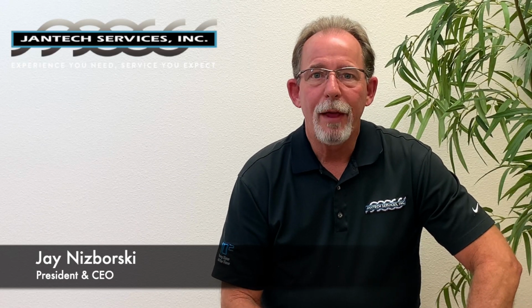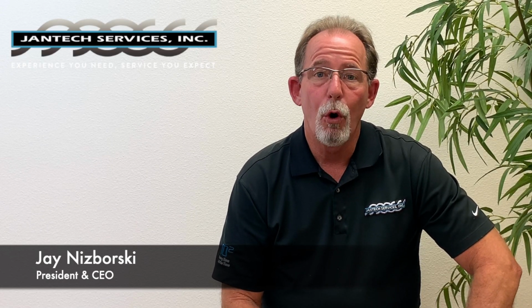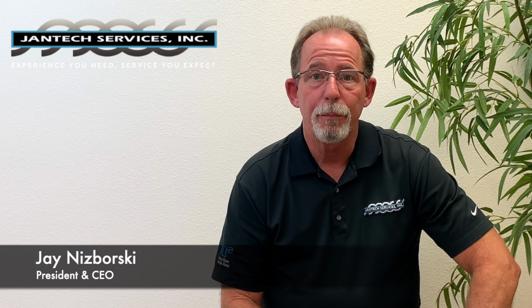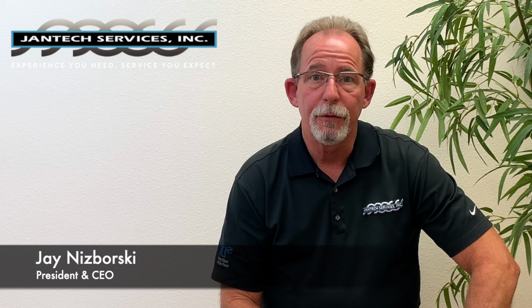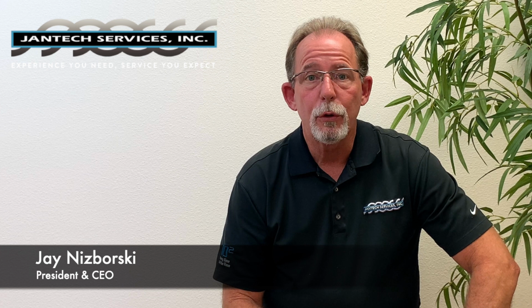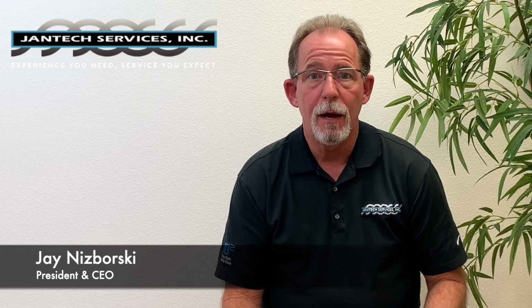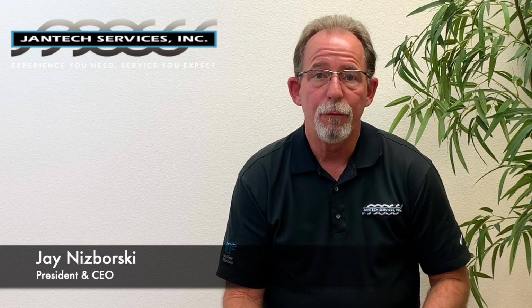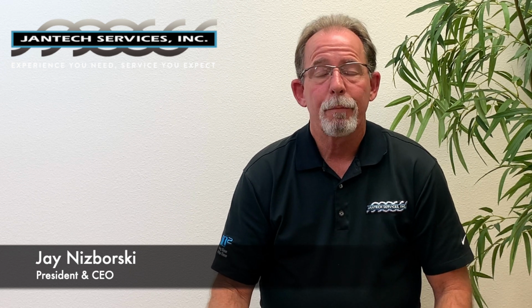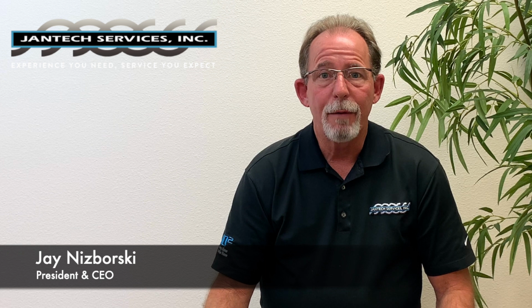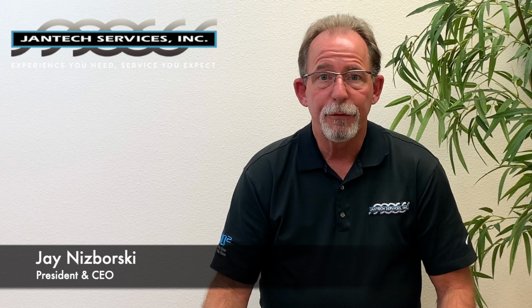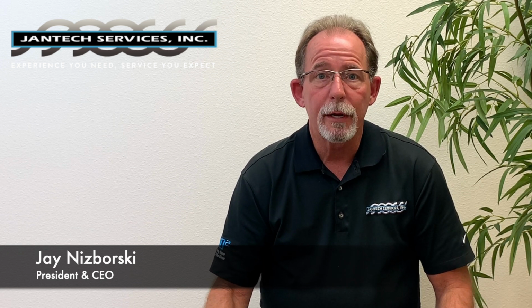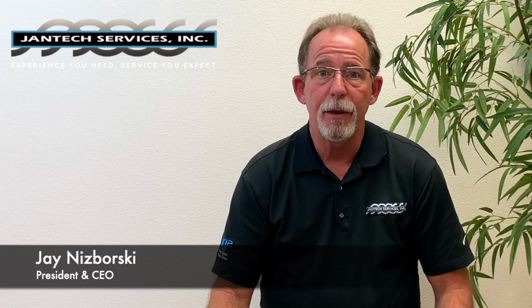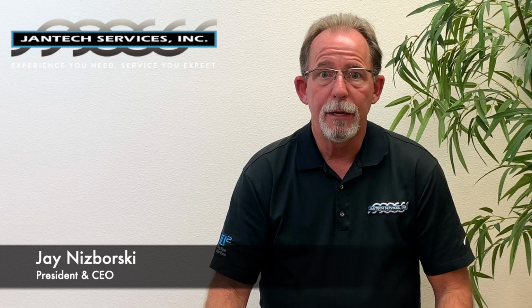So to close this out, I would highly recommend you always install an external maintenance bypass on your UPS. What configuration you can do, what your breaker availability will accommodate will dictate what configuration you go with. The less operator error you ever deal with and the more isolation you can provide to your critical load through that maintenance bypass is greatly going to enhance and benefit your facility's operation.